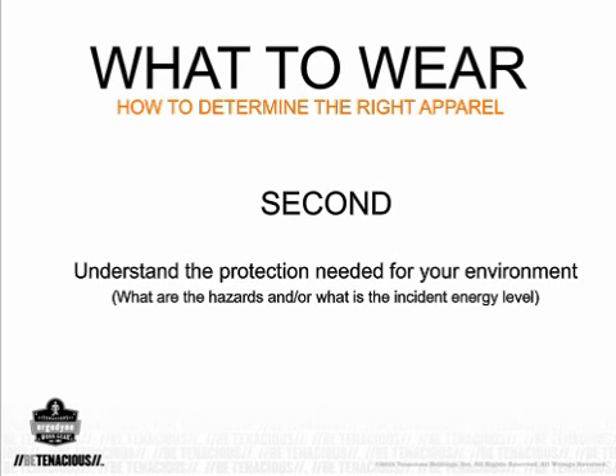Step 2: understand the protection needed for your environment. Once your risk assessment has been finalized, you should be clear on what hazards you and your team may face, and the incident energy level you need to protect your workers against. For example, the CAL rating—if your CAL rating is 8 or 12, you will need to have the appropriate apparel for that.